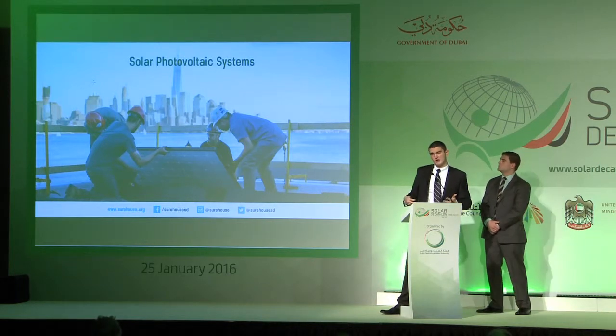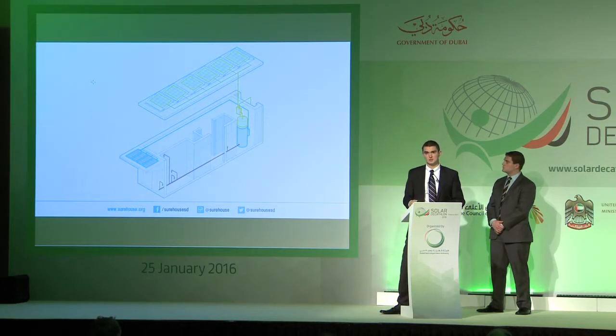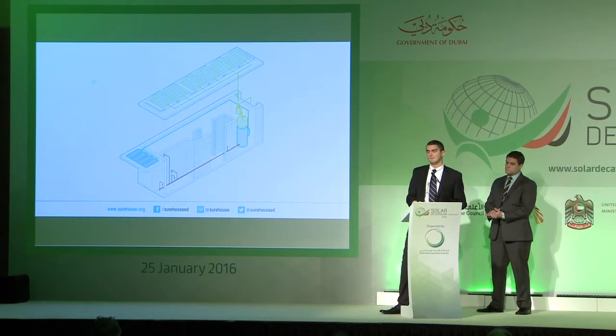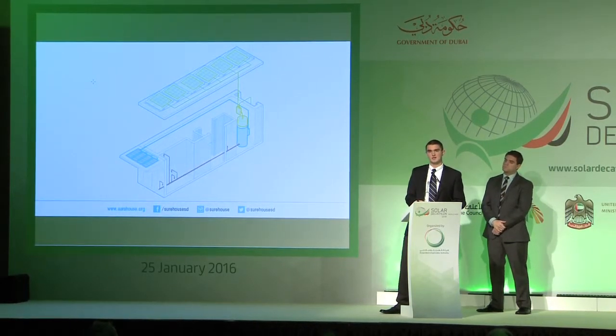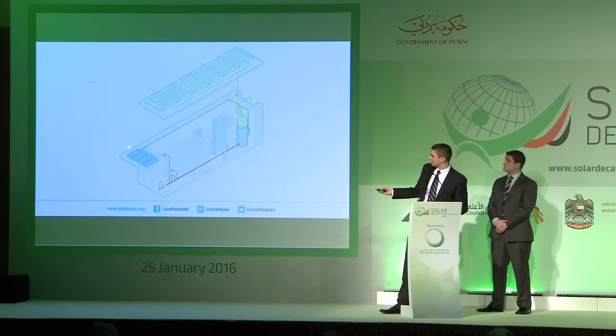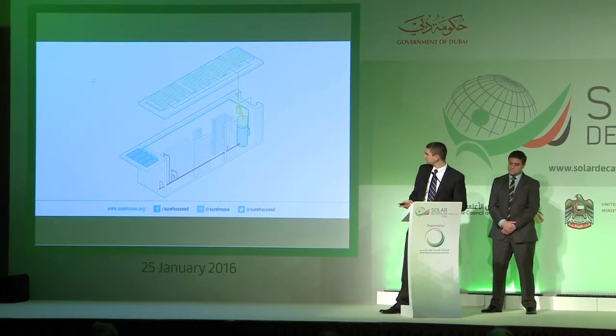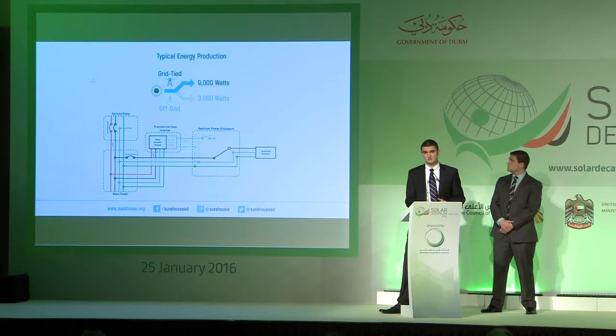So more about our energy systems. So we actually had two different types of solar arrays on the Sure House. One shown in yellow here was on our roof. It was a 9 kilowatt array. And then the second one on those storm shutters was about a 1.8 kilowatt array. The roof array, much like many homes have, was tied into a central inverter system and provided more than enough energy for the home, like I said, about 130%. And then that shutter array was direct DC energy that went into the lower heating element of our hot water tank. So the main array had the ability to do what's called island or isolate itself from the grid.